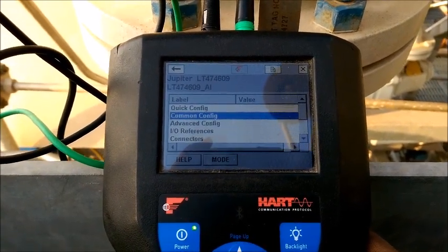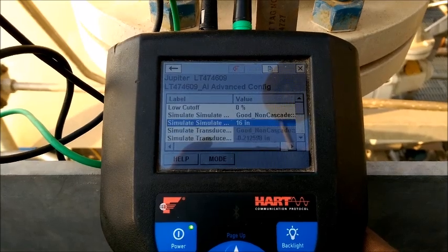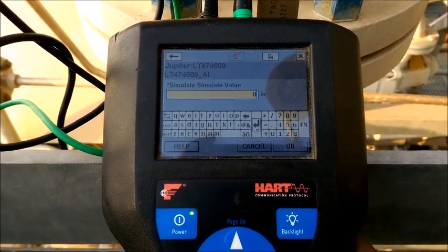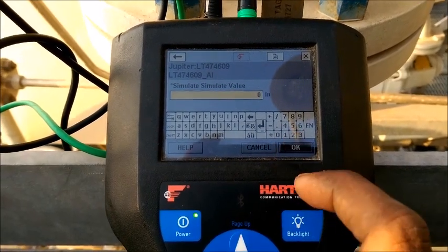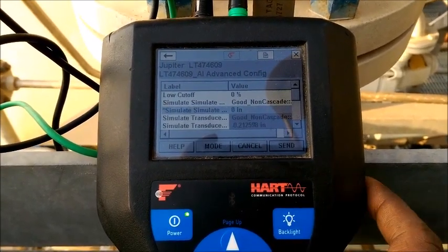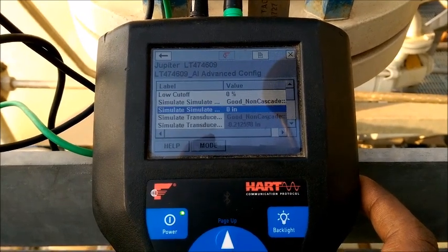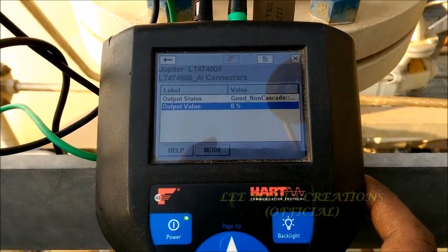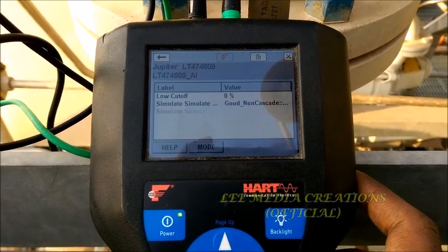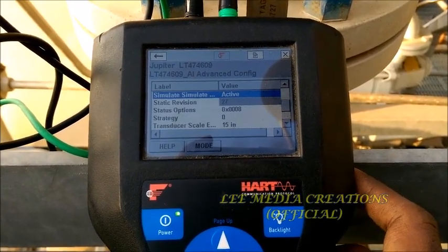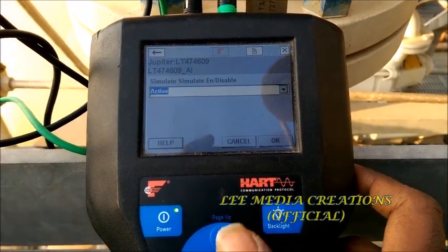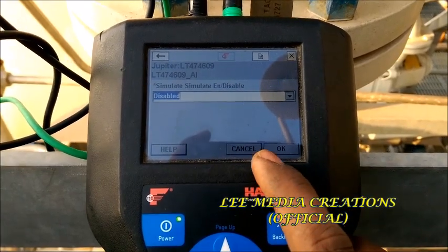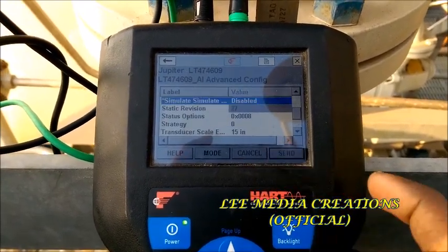Now I want to make it normal. Just go to advanced config, then go to simulation value and apply 0 — click OK and send. Now it is showing normal and comes back to 0 percent. You should now disable the simulation mode — go to simulation enable, set to disable mode, click OK and send.